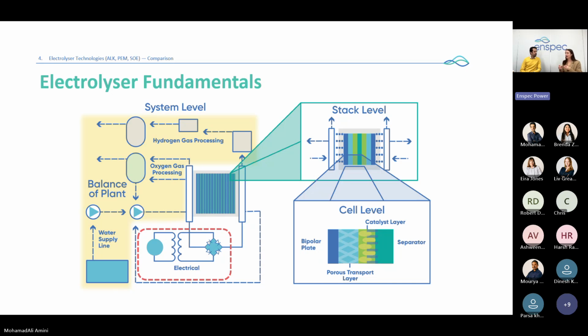It doesn't just impact the area at which it's connected, but can have a more regional, larger scale impact along the grid, because it's so large itself that you amplify the symptom from the fact that it's now a much bigger facility. So it's something that really needs to be considered as part of the design of the electrolyzer, ensuring that it does in fact meet the appropriate requirements as it's connected, because the impact can be quite catastrophic.